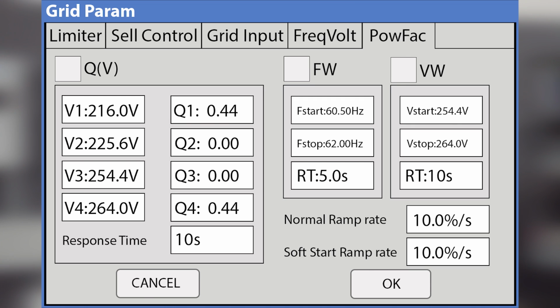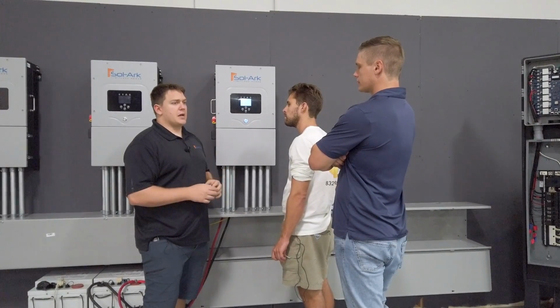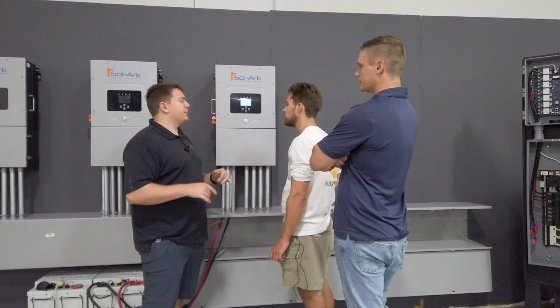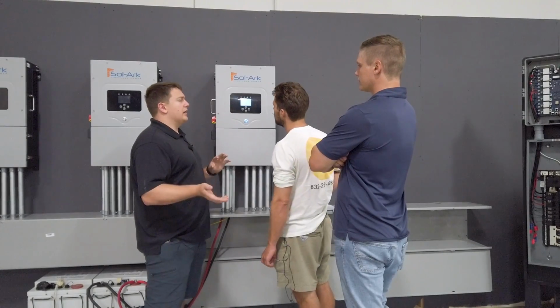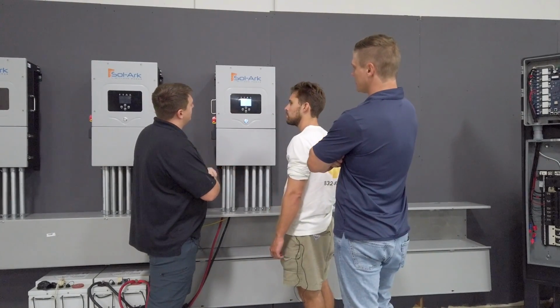Power factor—probably 95% of the time you won't have to touch anything on this screen. As part of regular commissioning, you probably don't have to do this. If you ever do have to come in here, sometimes enabling QV, which stands for dynamic power factor, can deal with some unusual events that happen when you're off grid with a bunch of LED lights that flicker a little bit. This will usually fix that. Anyways, these are kind of more obscure settings.